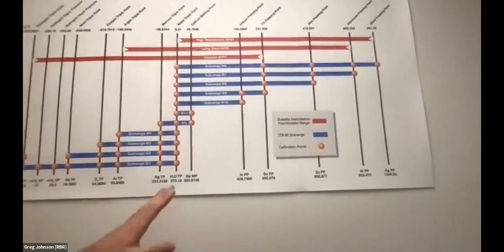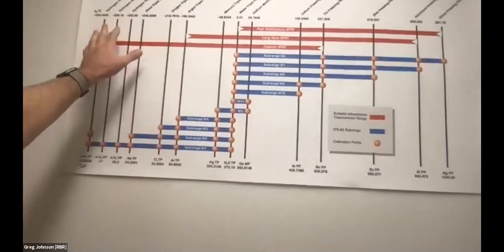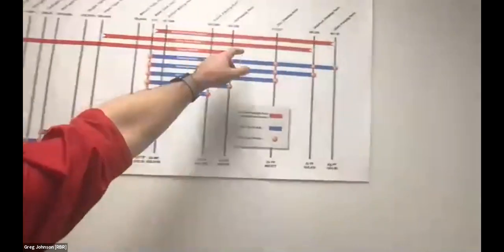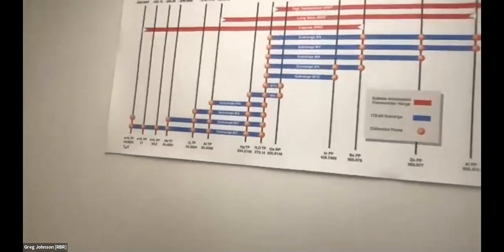Question then arises, okay, so you can calibrate against your SPRTs, and that's all well and good, but how do you know that the SPRTs are accurate? And we calibrate those against primary standards. Primary standards are physical artifacts where their intrinsic properties are those that we're going to use as temperature set points. And in fact, temperature scales, such as the ITS-90, which is behind me on the wall here, are defined by those primary standards. So the primary standards of the ITS-90 range from -259 up to just under 1,000 degrees Celsius.